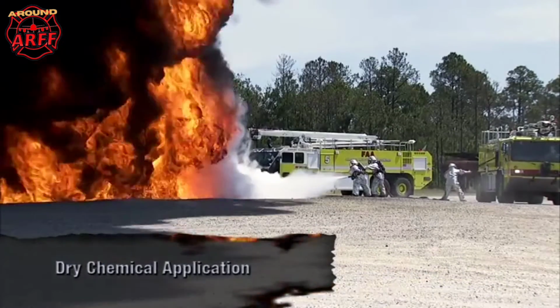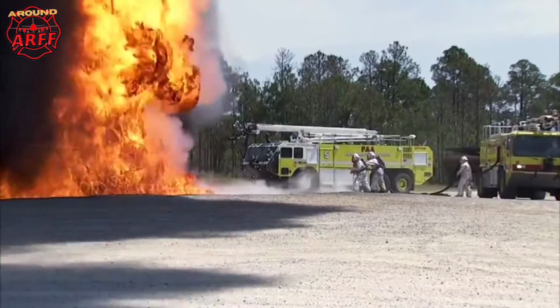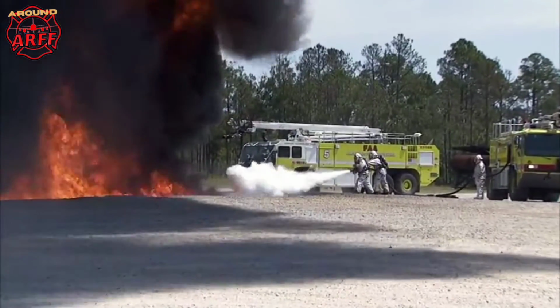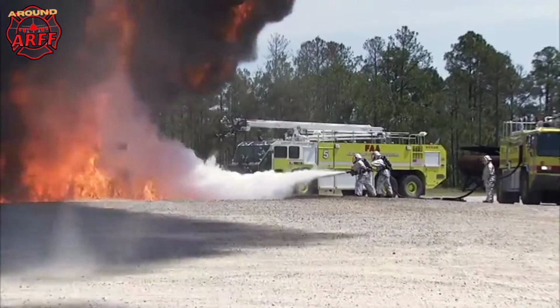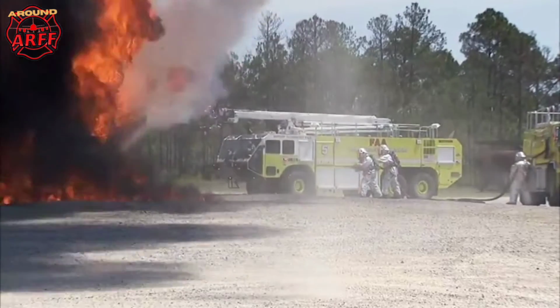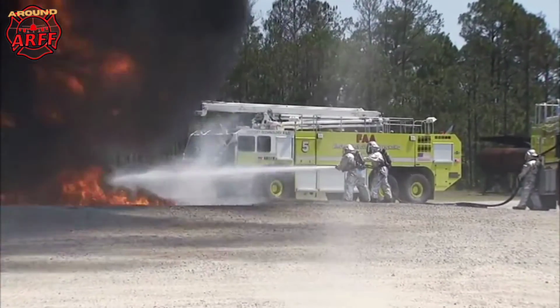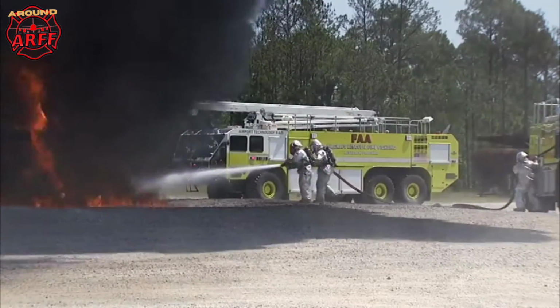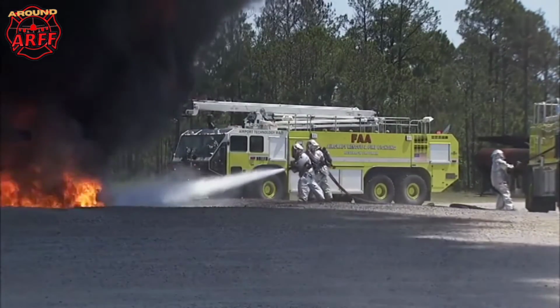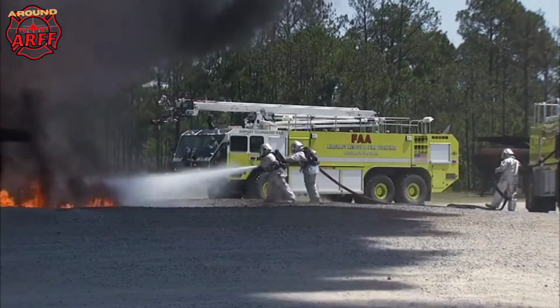Apply dry chemicals by directing agent at the base of the fire and sweeping the nozzle back and forth. Charge and test the system by discharging the agent before approaching the fire from upwind. Check range by discharging small bursts at the fire. Start the initial application from as far away as possible. Hand lines from large wheeled extinguishers and truck-mounted systems have significant nozzle pressure. Brace yourself and have someone back you up.